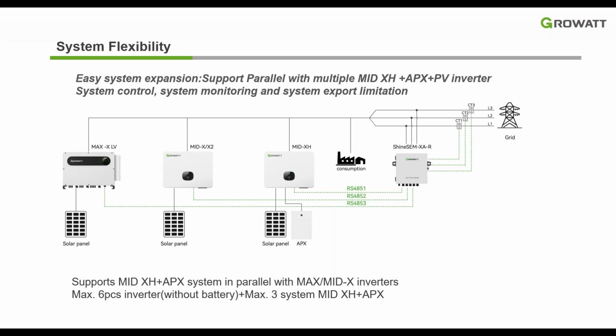But if you don't have batteries, by using our SEM, the Smart Energy Manager, you can connect up to nine inverters in total. We call it SEMX, the Smart Energy Manager. It comes with a Smart ShineMaster, which can monitor multiple inverters, up to 9 or even 10. It also comes with a 3-phase meter on the side. It can limit the power export to the grid. So do remember to add a SEM if you have multiple inverters. If you use multiple dongles, it doesn't work, because we have to control each of the systems to export to the grid. Only ShineMaster X and a 3-phase meter can meet the G100 regulation.